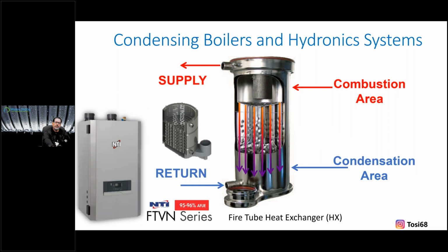So this is our fire tube, and this is, I'm sorry, that was our water tube, and this is our fire tube. So it's a little different design where it's in a downflow, right? If you see in the center there, that is the burner, and that whole chamber is just going to be loaded up with hot flue products, and then flowing through. If you're looking at smaller cross sections, you see the perforations, like a strainer, and all of that is now getting forced with the blower down through these channels, which are now surrounded by the water. Again, we have the hottest against the cool return, and that's now the big sponge. That cooler water will allow more absorption of all that heat energy into the water, which we want.